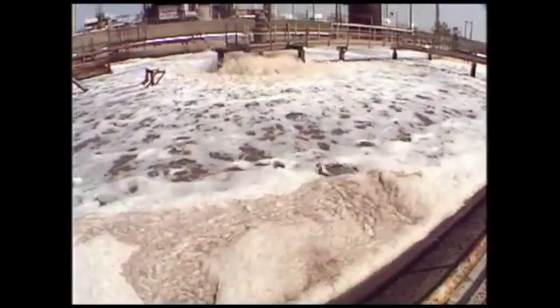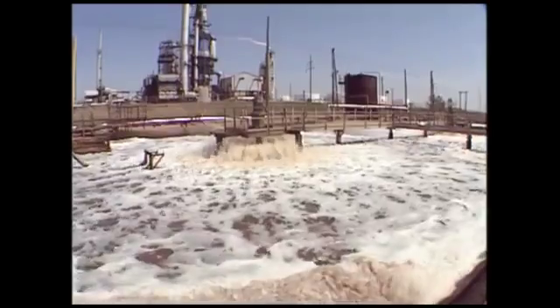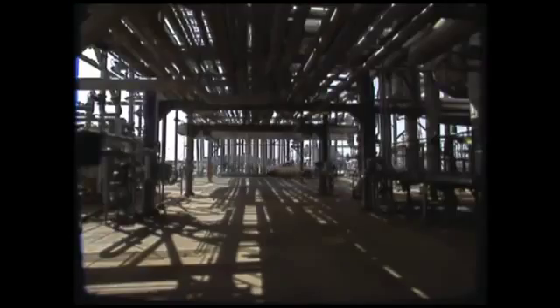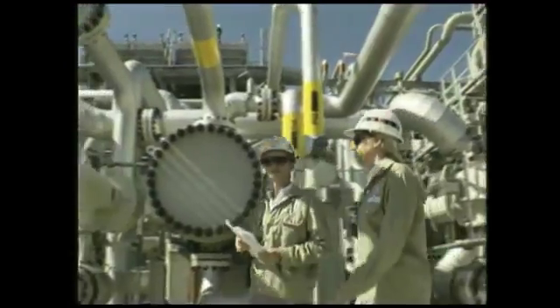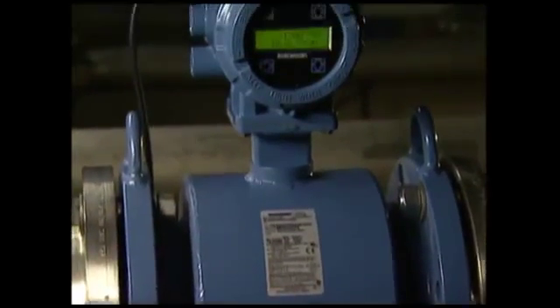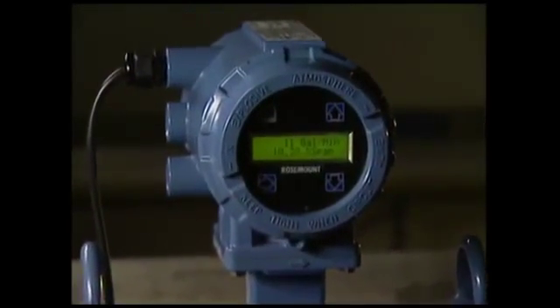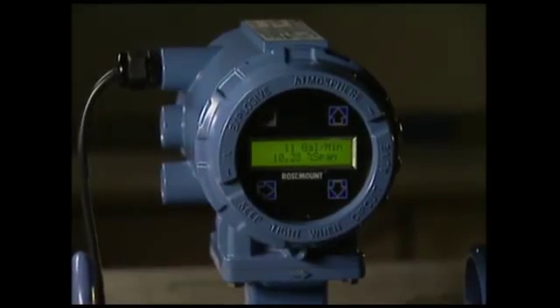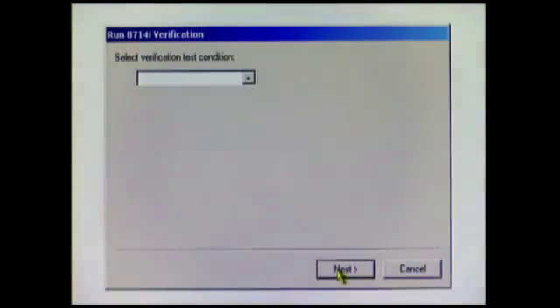Accurately verifying flow meter calibration is important for many users, whether to meet government regulations or their own internal quality standards. Meeting this requirement can be costly and time-consuming to implement. Rosemount E-Series magnetic flow meters are available with the patented 8714i calibration verification diagnostic. This allows you to verify the entire meter calibration without removing it from the line or buying extra equipment.